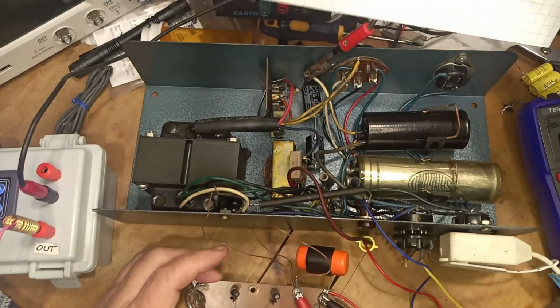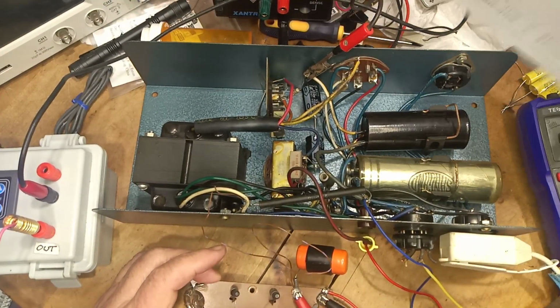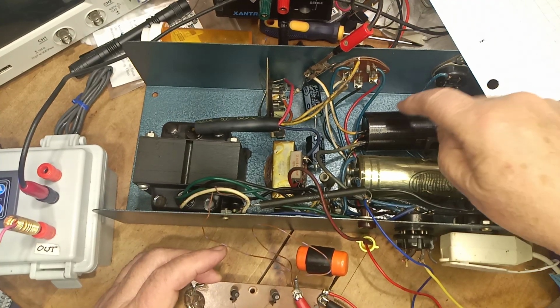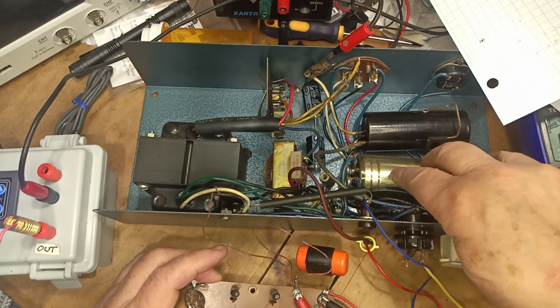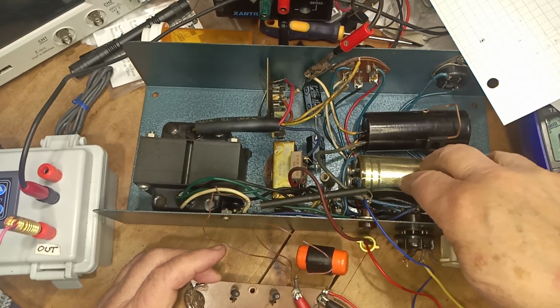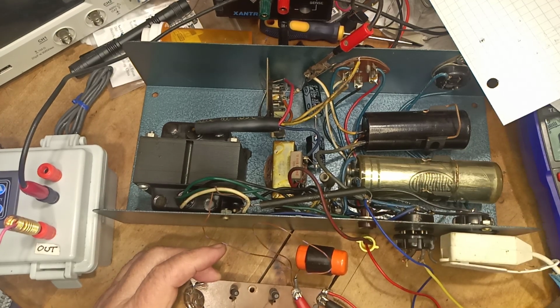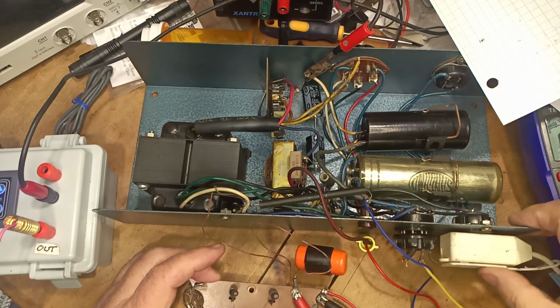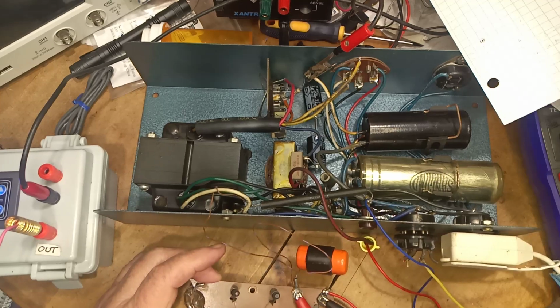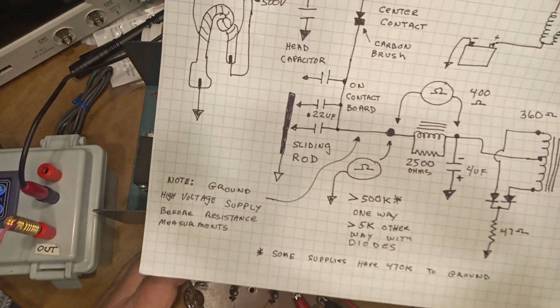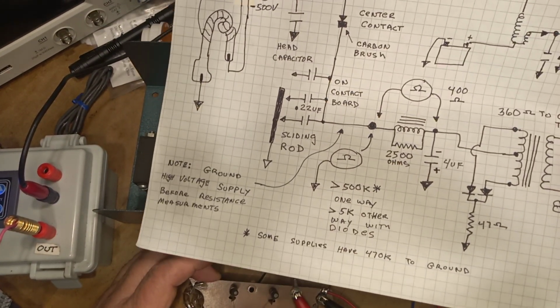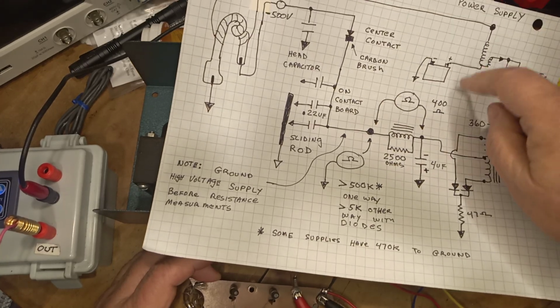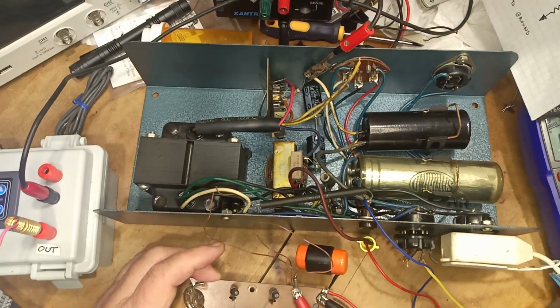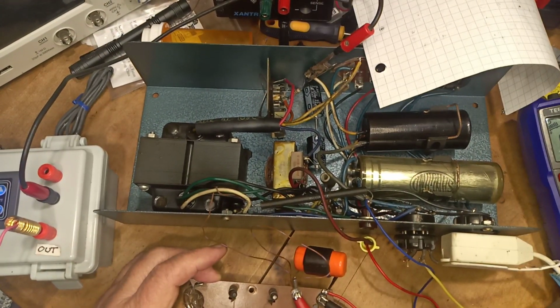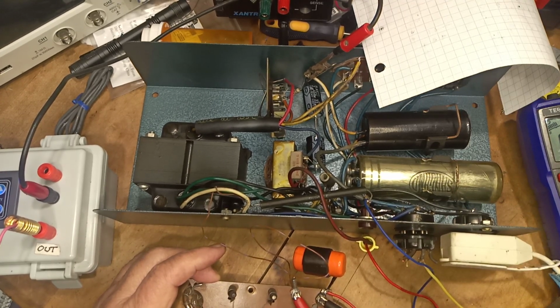And again, if it has the internal power supply, some of these are totally battery operated. This one provides about 8.4 volts. When you apply a load to it, in other words your points are closed, the voltage will drop down to about 4 or 5 volts. So you want to have some voltage that appears on the lead that comes out to go to the points.